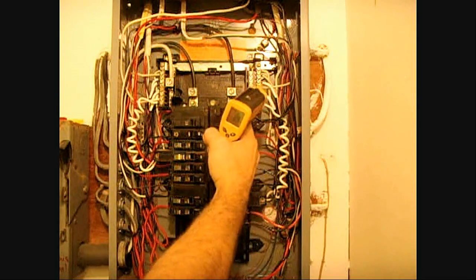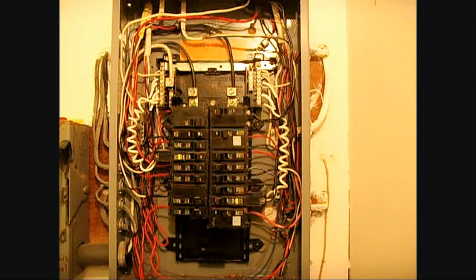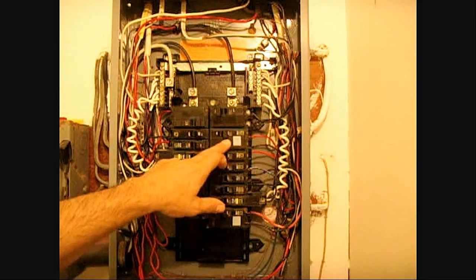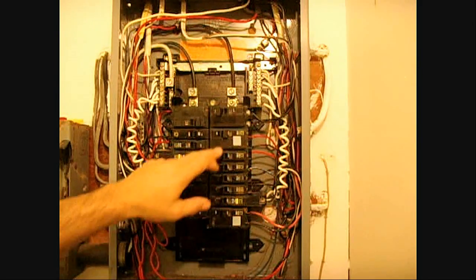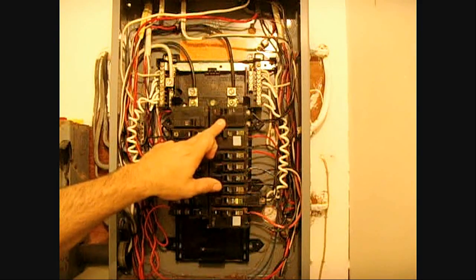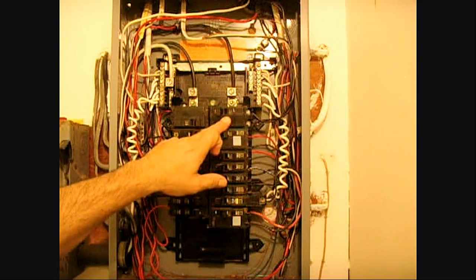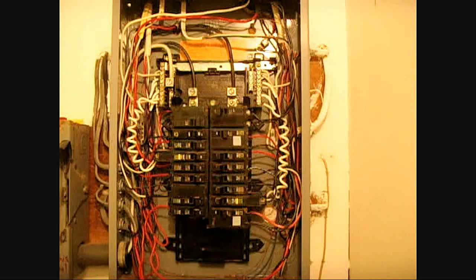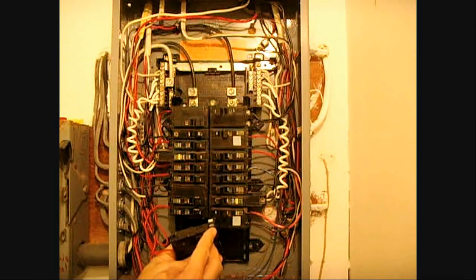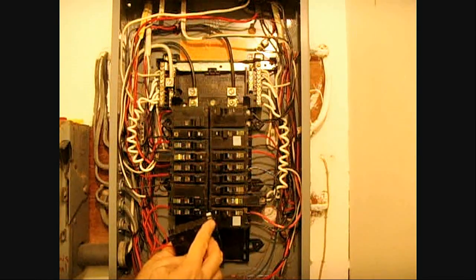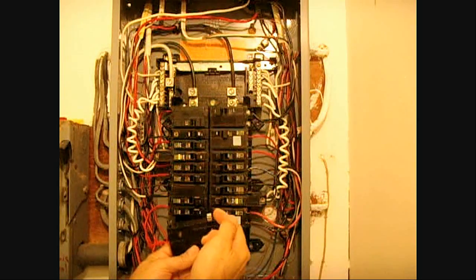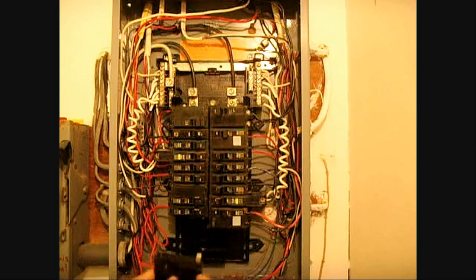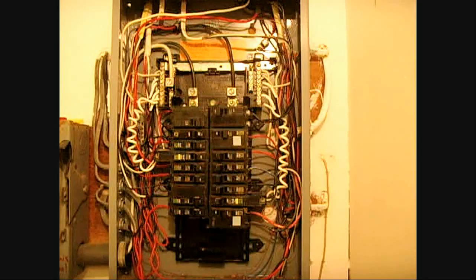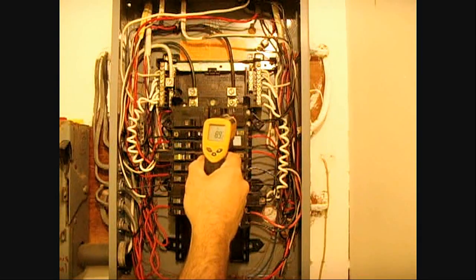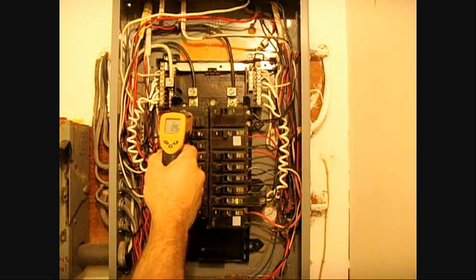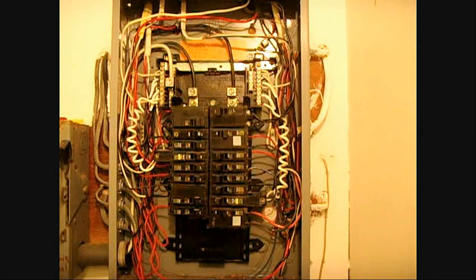It's normal for circuit breakers to run warm, especially if you're running near the full rating of the breaker or close to it. It's not normal if the breakers are hot. If the breakers are getting hot, that would more than likely indicate, like I said earlier, that this clip is probably very corroded and it's a high resistance connection and the current is heating up the whole breaker as well as the bus bar. So you're going to want to check that out. So you can see 89, 89, everything's the same, that's fine.